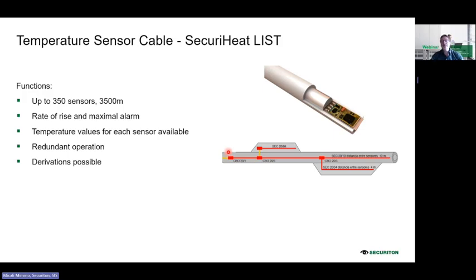Derivations are also possible. When you install the cable in a tunnel, you can also make derivations if you have to protect, let's say, a platform in a metro station, a parking area inside the tunnel, or a gallery which makes the connection between two tubes. This derivation can be done during the installation, but it is also possible to do such a derivation after you install the cable. So this is very flexible.